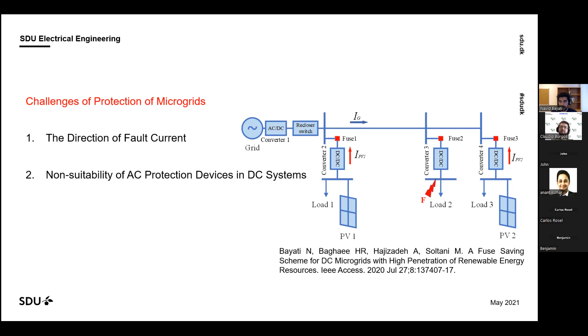Also, when we talk about the converters, they cannot work too much on high fault current. So if we have a fault in, for example, load 2, converter number 3 cannot work too much on the huge fault current. So we have some limitation in the capability of the converter. They can limit the current when we have this kind of fault. And when we need the data or sensors from all converters, converters 1, 2, 3, and 4, to find the fault current or current in the system, we need for sure some communication links. And communication links create some challenges, for example, noise and delays.